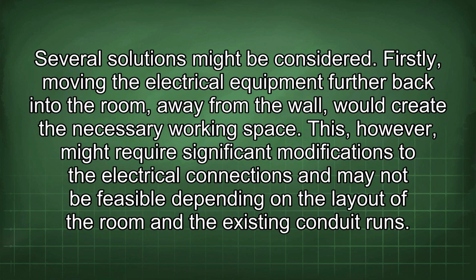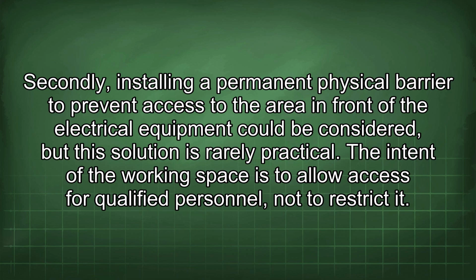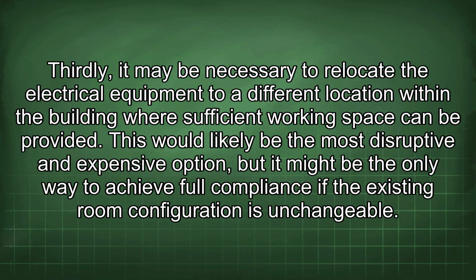Several solutions might be considered. Firstly, moving the electrical equipment further back into the room, away from the wall, would create the necessary working space. This, however, might require significant modifications to the electrical connections and may not be feasible depending on the layout of the room and the existing conduit runs. Secondly, installing a permanent physical barrier to prevent access to the area in front of the electrical equipment could be considered, but this solution is rarely practical. The intent of the working space is to allow access for qualified personnel, not to restrict it. Thirdly, it may be necessary to relocate the electrical equipment to a different location within the building where sufficient working space can be provided. This would likely be the most disruptive and expensive option, but it might be the only way to achieve full compliance if the existing room configuration is unchangeable.